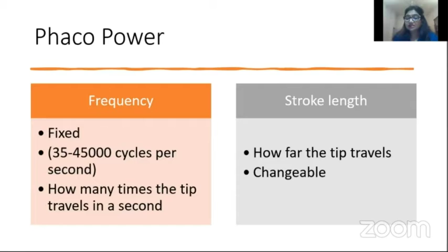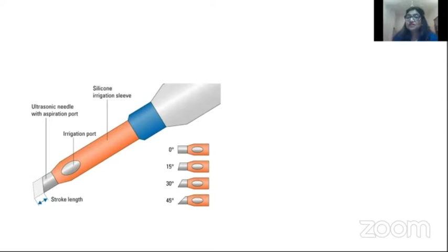The tip also has different degrees. A 0-degree tip will have more holding or can create more vacuum easily, whereas the cutting will be less. Whereas a 45-degree tip will have better cutting, but will be able to hold the piece less easily. So these are the different types of tips which can be used in different grades of cataract. Then you have the jackhammer effect, which is basically a physical force that helps when the tip and the nuclear fragment come together.